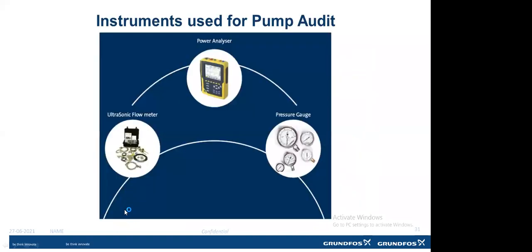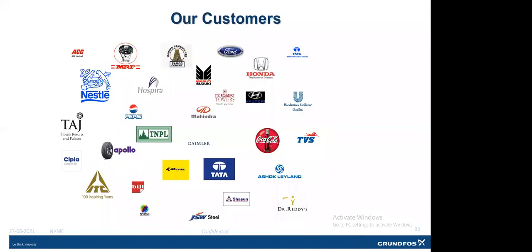And we have these sets of instruments. We use our calibrator, ultrasonic flow meter, power meter, and pressure gauges. Pressure gauges are used for head, power meter for measuring the power, and flow meter for the flow. And these are the customers.